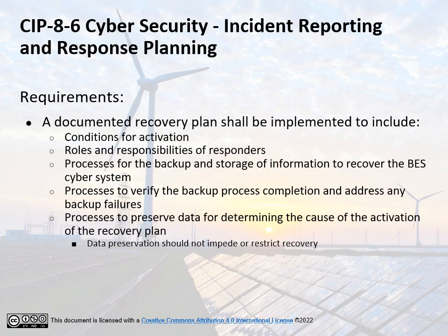CIP-009-6 Recovery Plans for BES Cyber Systems. Requirements: a documented recovery plan shall be implemented to include conditions for activation, roles and responsibilities of responders, processes for the backup and storage of information to recover the BES cyber system, processes to verify the backup process completion and address any backup failures, processes to preserve data for determining the cause of the activation of the recovery plan, and data preservation should not impede or restrict recovery.